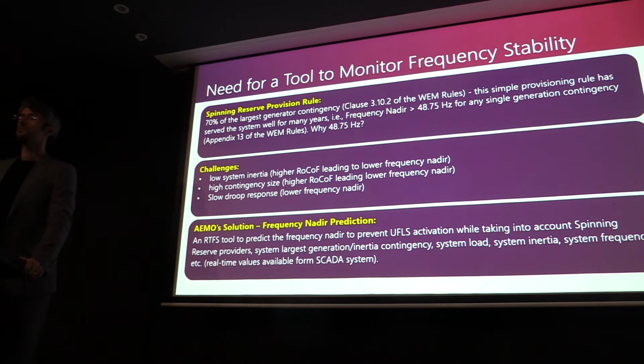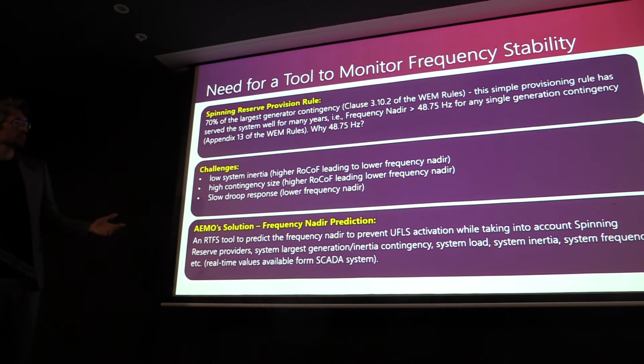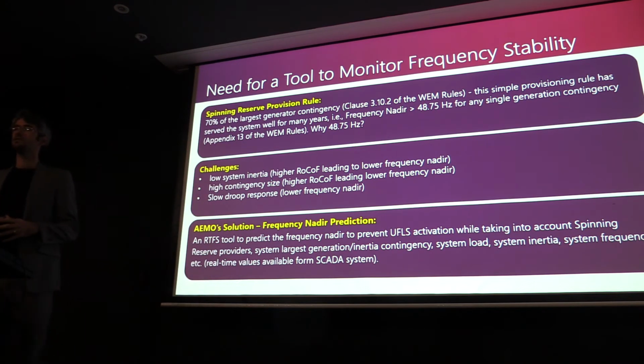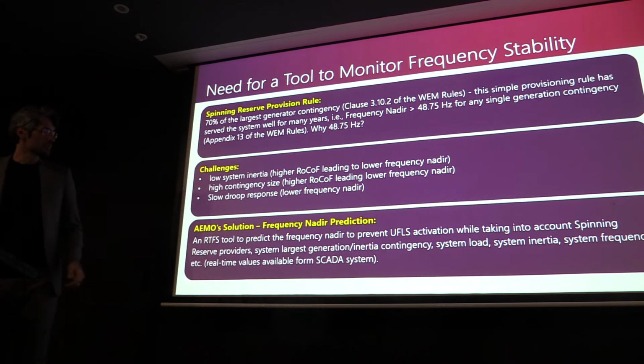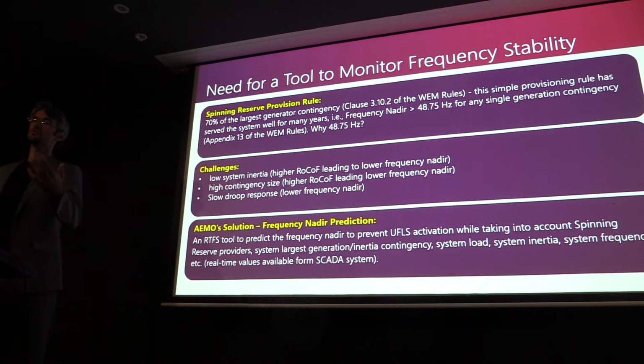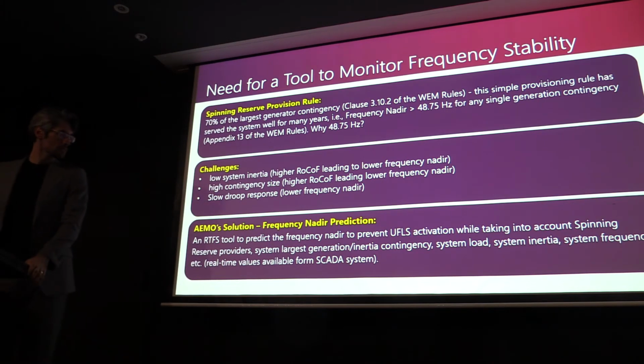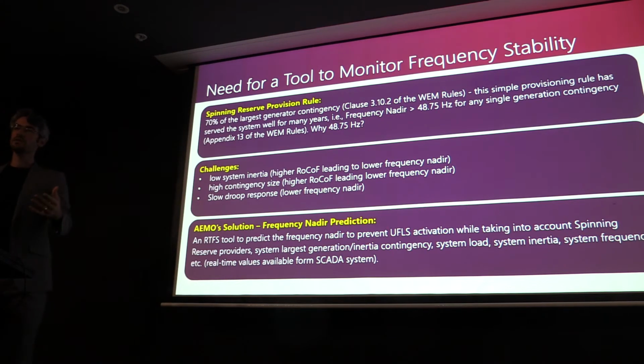So our solution, based on the research and all the work we've done, is the tool we've developed. In real time we consider all the real data, like system load and system inertia, and we consider the largest contingency size. That contingency could be the generator with the largest megawatt or the generator with the largest inertia. We predict the frequency. If we identify that for any largest generation contingency we will have a non-secure state, or we will breach the requirements, we try to fix it in real time.